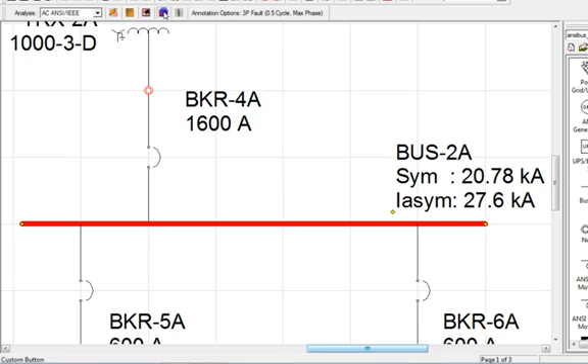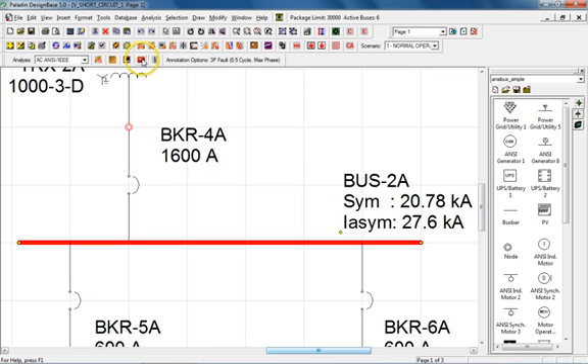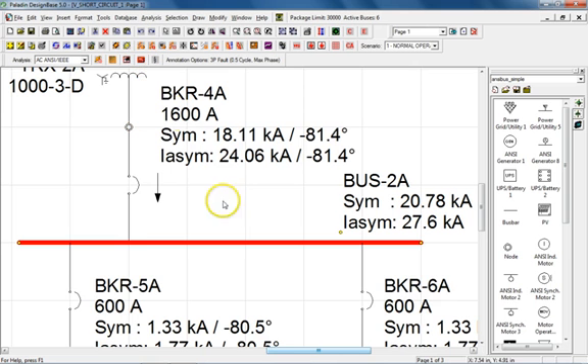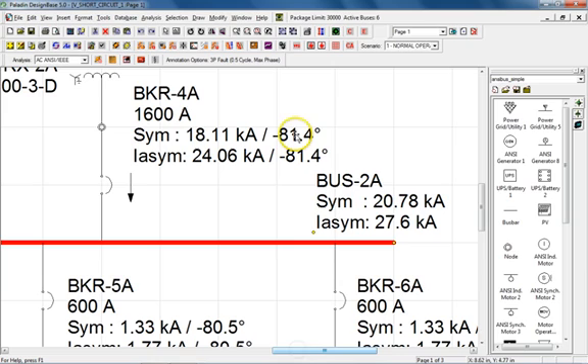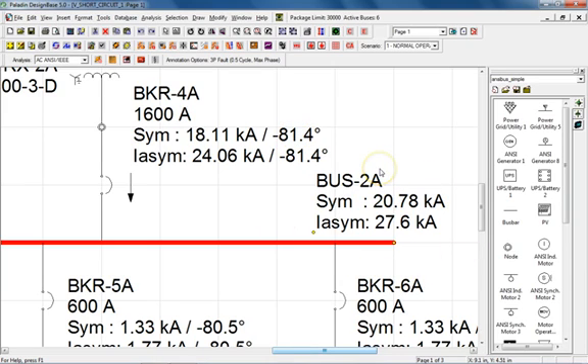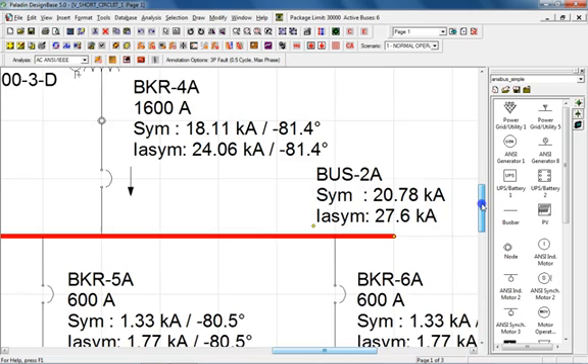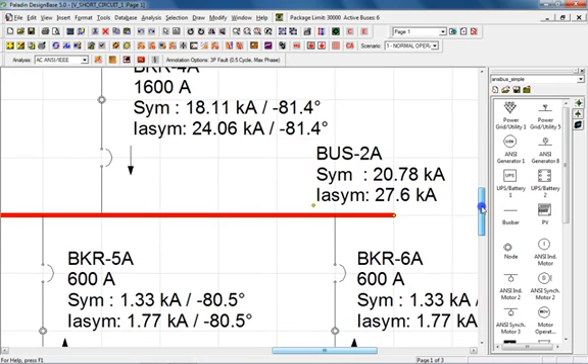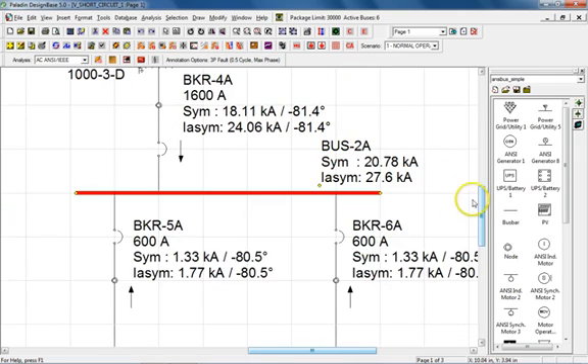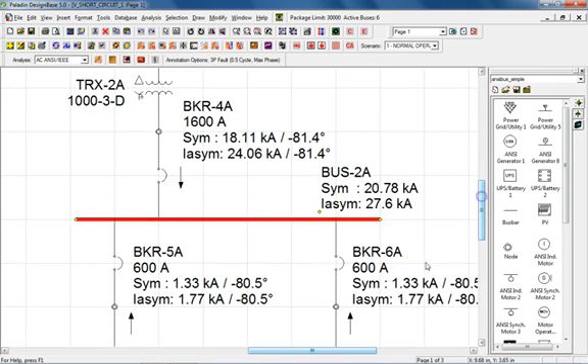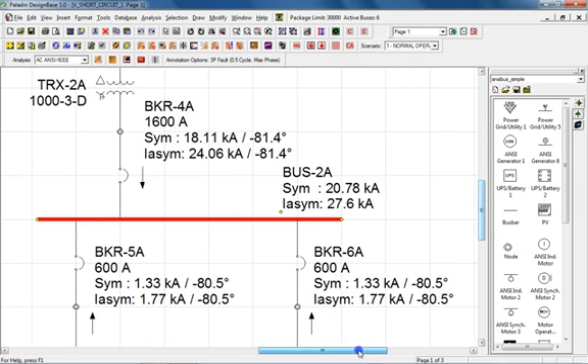Notice that when selecting a single bus, we can display a lot more information about the fault. In this case, we can see not only the bus fault current at bus 2A as indicated here, but also the upstream and downstream branch contributions for the half cycle time band along with flow arrows and the electrical phase angles.